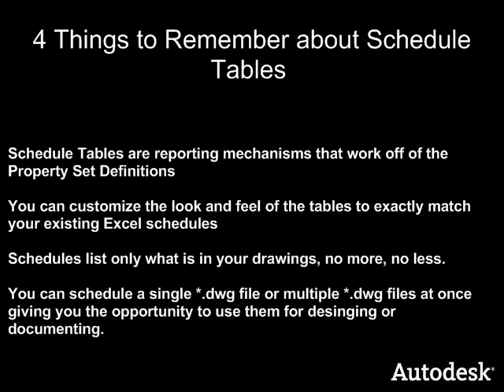Four things to remember about schedule tables. Schedule tables are reporting mechanisms that work off of the property set definitions. You can customize the look and feel of the tables to exactly match your existing Excel schedules. Schedules list only what's in your drawings. No more, no less. You can schedule a single DWG file or multiple DWG files all at once, giving you the opportunity to use them for designing or for documenting.